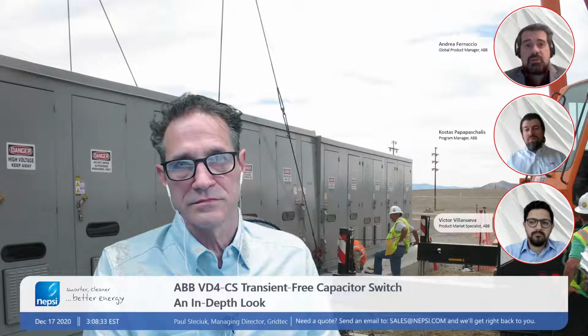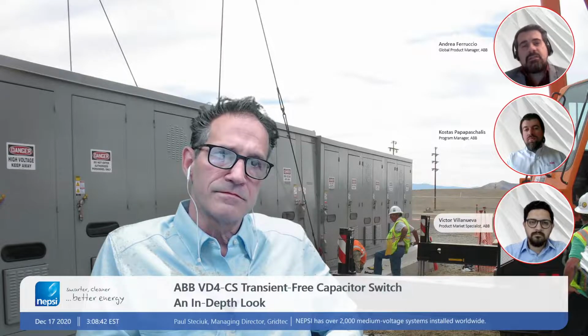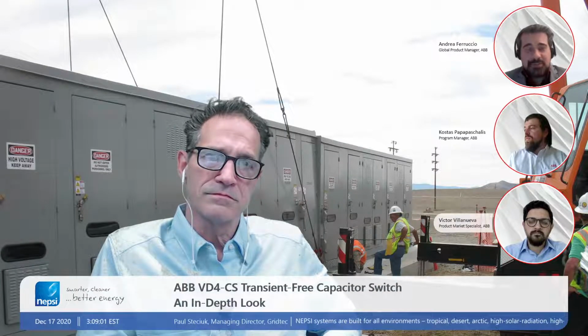During the short circuit events, we can count on the VD4-CS thanks to its short circuit breaking capability. And then clearly the short circuit event will be cleared in a simultaneous way. It means that without any synchronization, the breaker, once it realizes that there is a short circuit, will open all three phases altogether. The synchronization instead is clearly working during the switching of the nominal capacitive current, which we have up to 1250 amps, which is very, very high. And we have also the possibility to open it in a non-synchronous, simultaneous way, using another input, another opening command, which is basically the redundancy of the first opening input we have on the VD4-CS. We have a second one that the user can use directly by inputting an opening command in case no synchronized operation is needed at that moment. Great. All right.